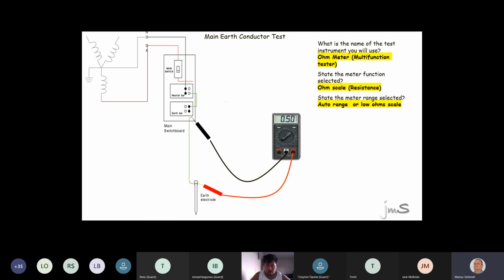So let's confirm. For a low ohm reading, you put it on a low ohms range and you're going to get a reading. After that, low ohms. Now the reason we say that, many moons ago in some multimeters, you could choose ohms, kilo ohms, or mega ohms. You could choose the range. It was not auto. And that's where that question came from. You put it on the lowest ohm scale.